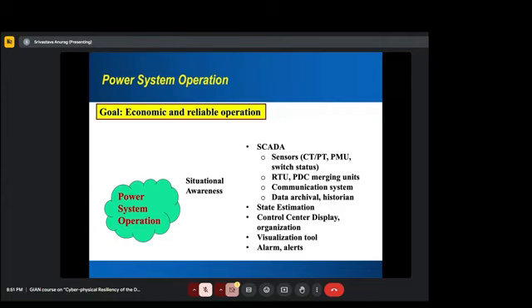SCADA includes sensors we've already discussed - CT and PT, current transformer, potential transformer - PMUs, and switch status, which we also need information on. Switch status doesn't come directly from the switch but from a digital sensor; a relay can tell us if a switch is open because it's already connected to the circuit breaker. RTU, the remote terminal unit, collects data and brings it to the control room. PDC, the phasor data concentrator, collects data from PMUs and brings it to the control room. The merging unit combines many digital signals at the substation and sends all the information in digital format to the control room. All of these have different objectives but are basically for sensing and collecting data.